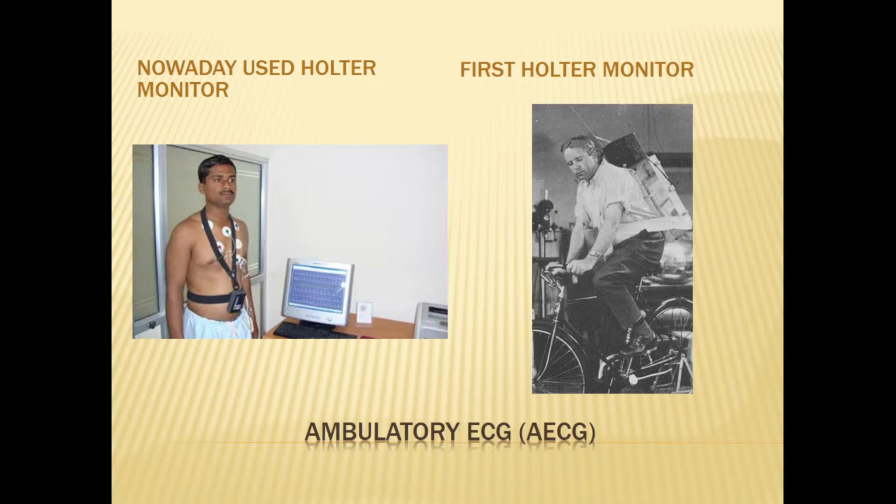You see, we place the monitor, a small computer device with different programs, on the patient's waist and connect it with electrodes placed on the patient's chest. Mostly, there are three leads in the most commonly used 24-hour ECG monitors. And for these three leads, we need 7 electrodes.